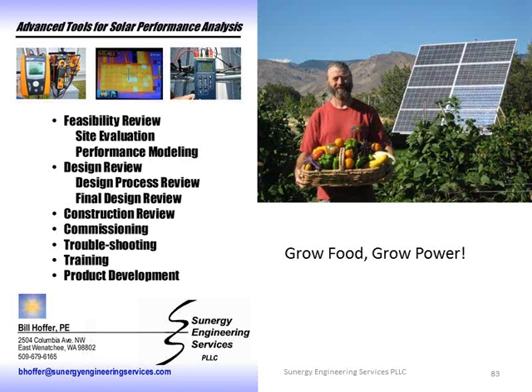Have you found any of these to be better for testing down at the inverter rather than up on the roof, especially when going back and recommissioning after the fact? Sometimes it's pretty hard to get to the combiner. It's like you have one person just doing a test down at the inverter, because a lot of these are more European style where you're doing MC4 connections, since Europeans usually bring the MC4s right into the bottom of their inverter. Right, and that's what they're designed for. So finally they're starting to make modifications where you can add a clamp-on, so you can go into a combiner box or into an inverter and do the test through that. Sometimes it's challenging, but most of the time I do try to do them at the inverter, that's usually the easiest place, or at the combiner box.